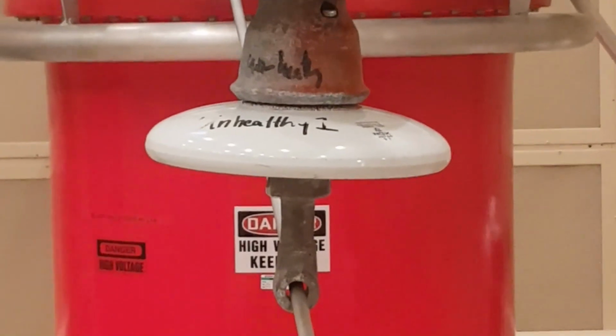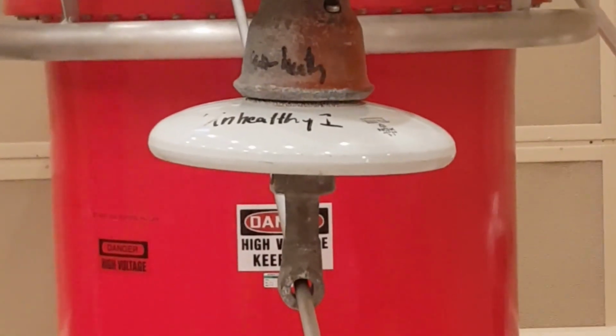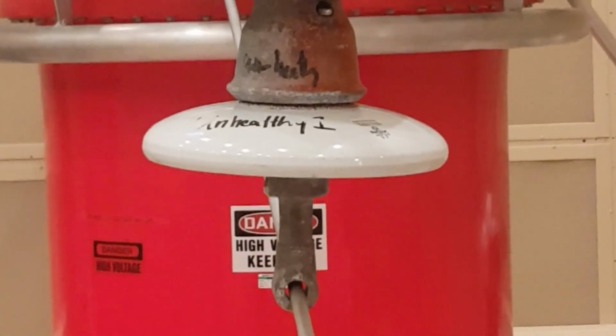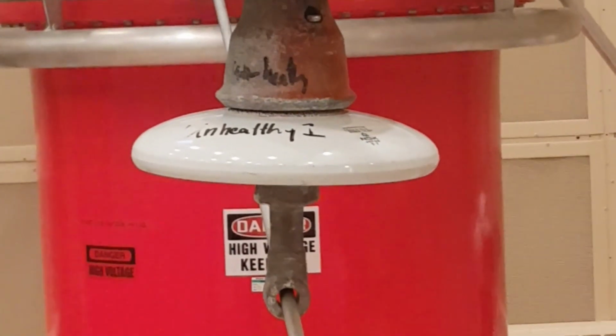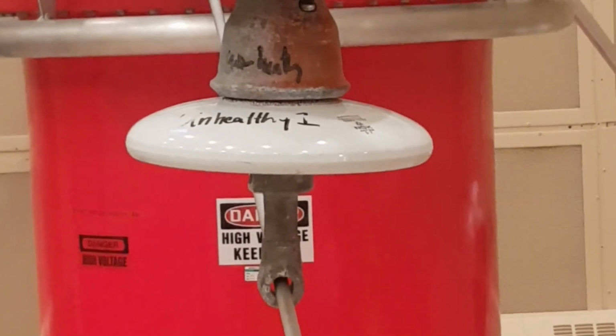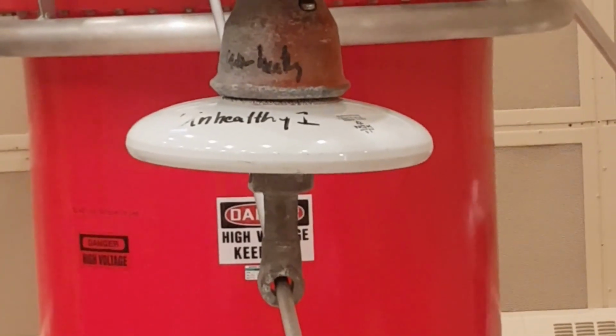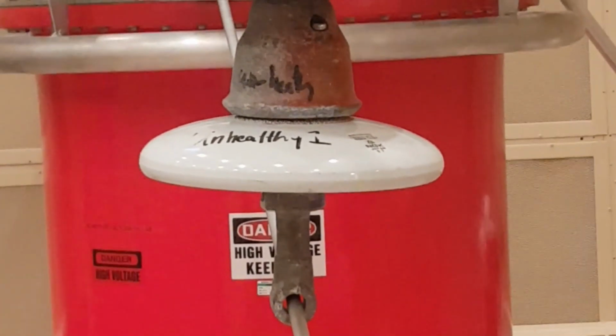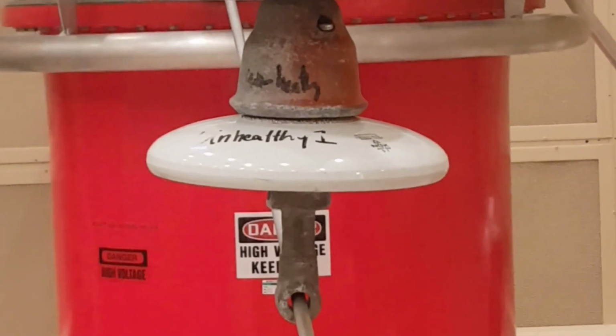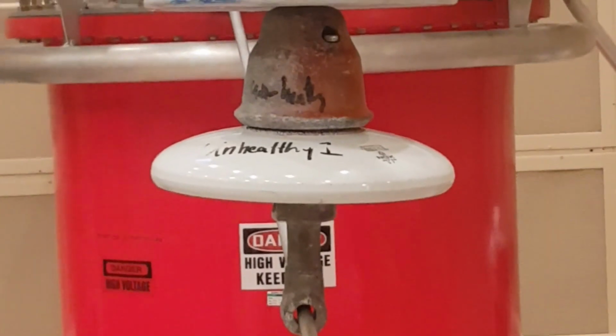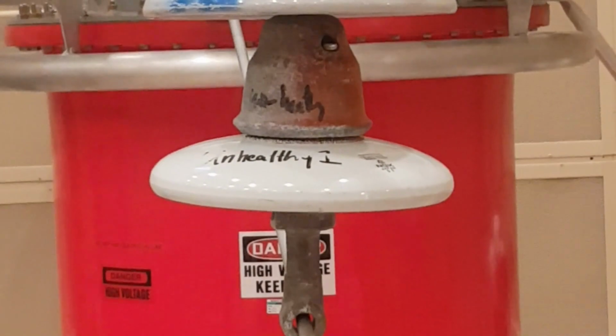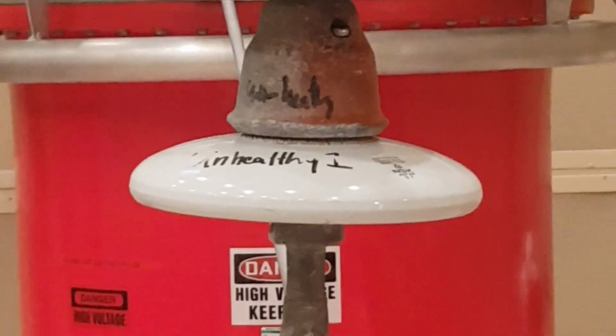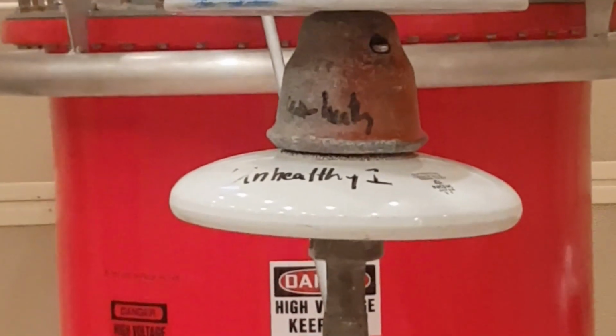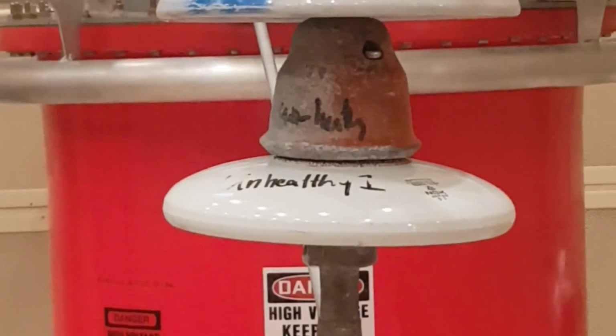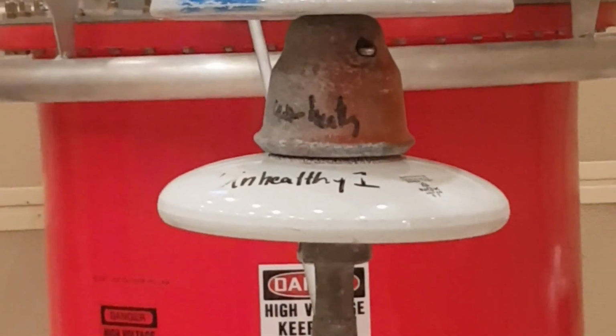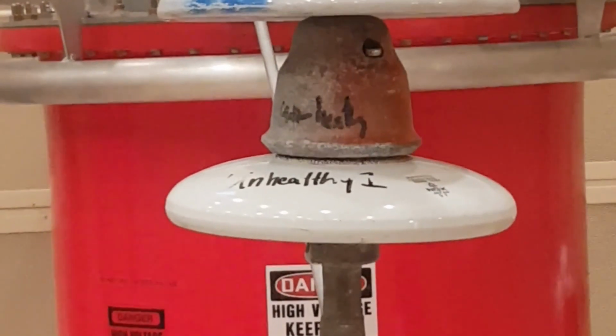Now we replaced the disc near the high voltage side with an unhealthy one. For this unhealthy disc, the tan delta was measured and it shows a very, very high value. We did this measurement in another video, and I will leave the link to that video in the video description. Now let's see what the PD level is when we energize the insulator at 30 kilovolt.